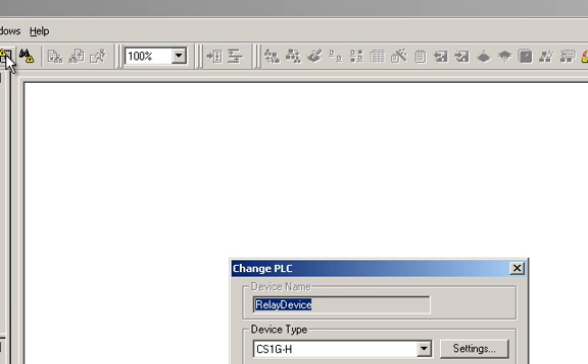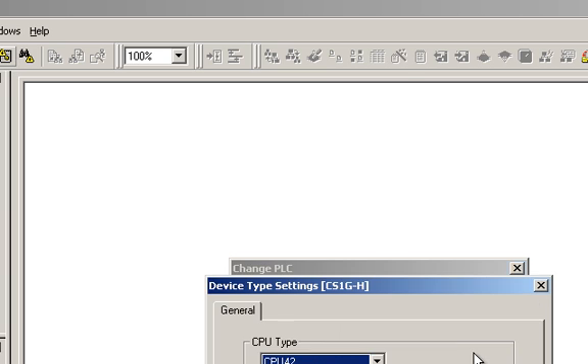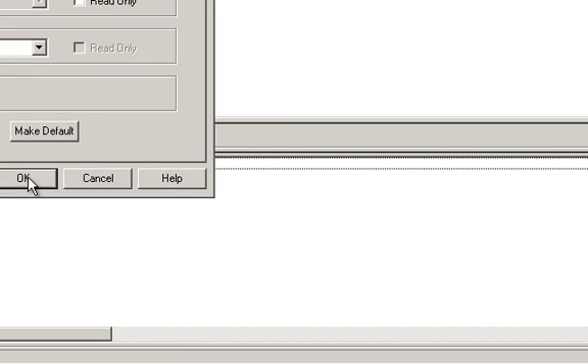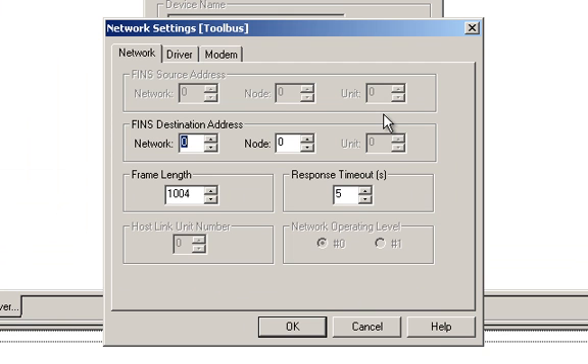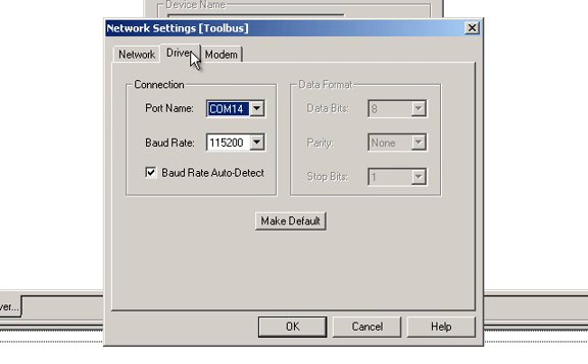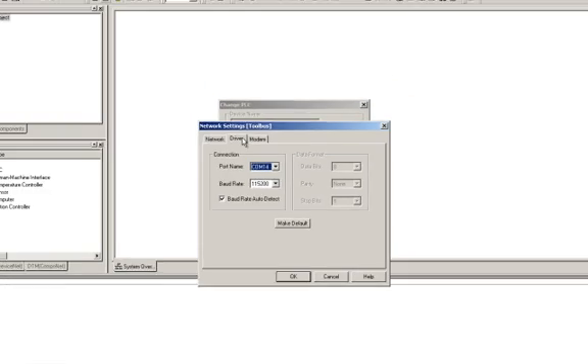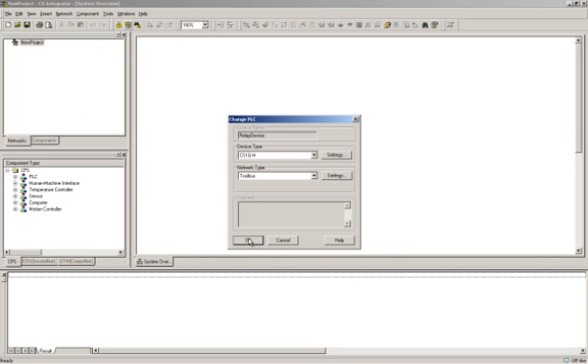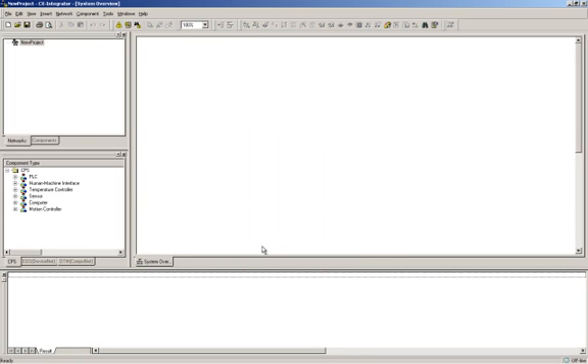Configure the device type. In my case, it's a CS1G-H PLC. Click Settings and choose the CPU. It is a CPU42. The network type that I will use to connect to the PLC is the Toolbus Binary Serial Protocol. To configure the COM port that I will use, I click Settings and go to the Driver tab. When you're finished, click OK and OK.